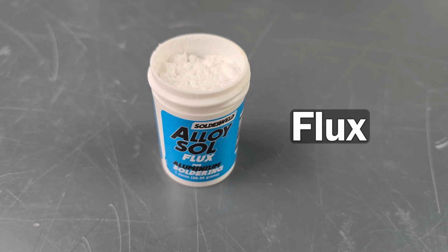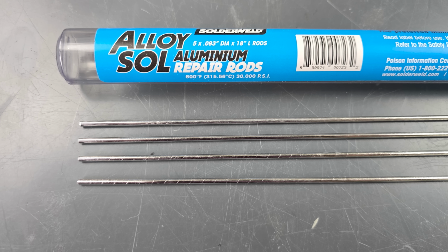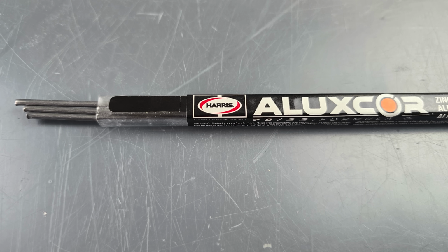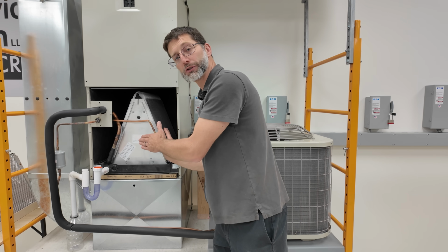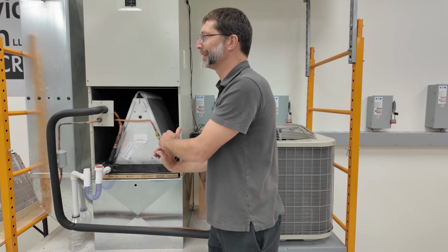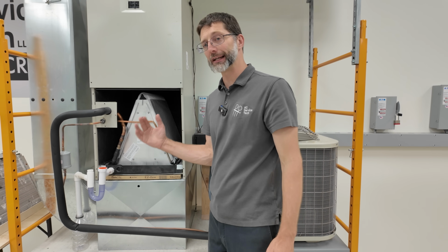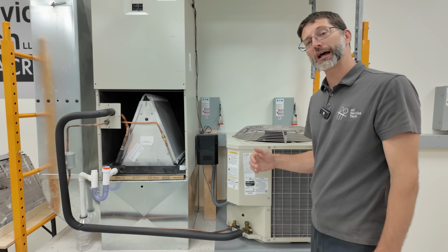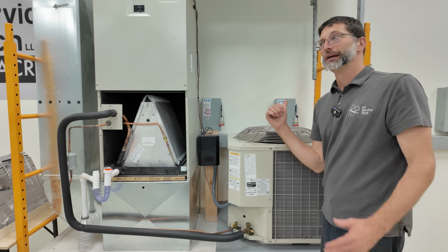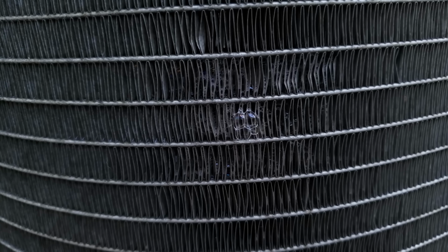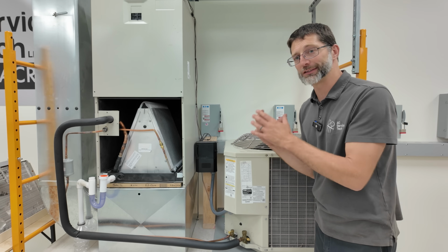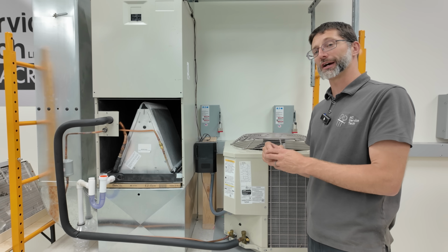And so you'd use the same rod to fix a leak with this as you would with the aluminum tube with aluminum fins. Now, an evaporator coil that's microchannel, we don't seem to be having that much trouble with those as far as leaks, but if you live near the coast and you have microchannel outdoor coils, that may be a problem. At least in my experience, I've seen a lot of leaks occurring due to the thin outer wall of the microchannel coil, even though they maybe are cladded with zinc in order to protect from corrosion.